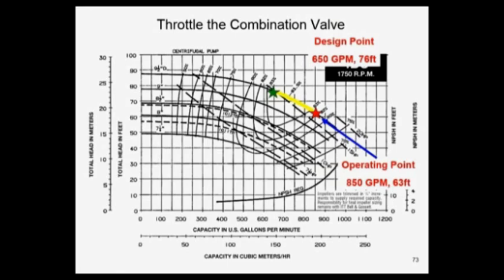My system curve was actually 63 feet, but I'm going to add some pressure drop through it by going through this throttling valve, I'm going to push it back up to 76 feet. Now I'm at 650 GPM, I'm now back at design. Great!